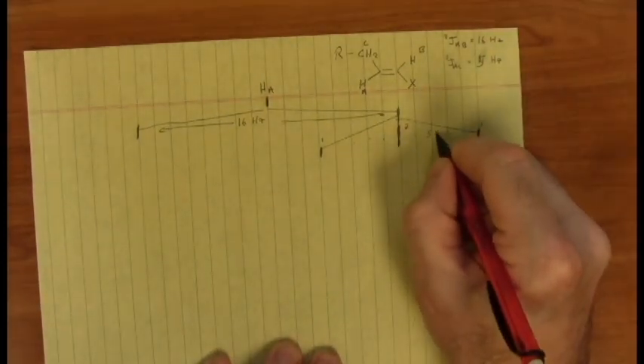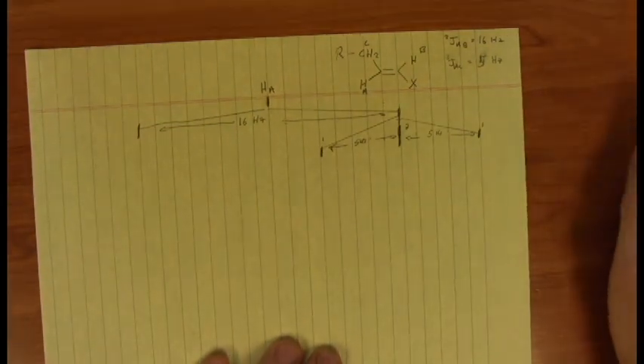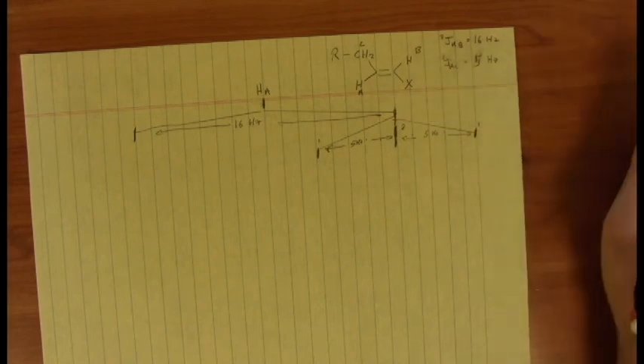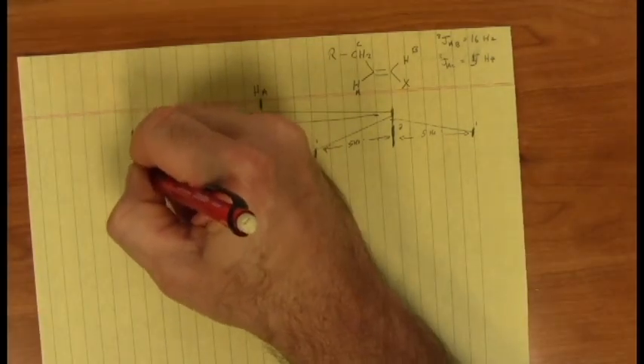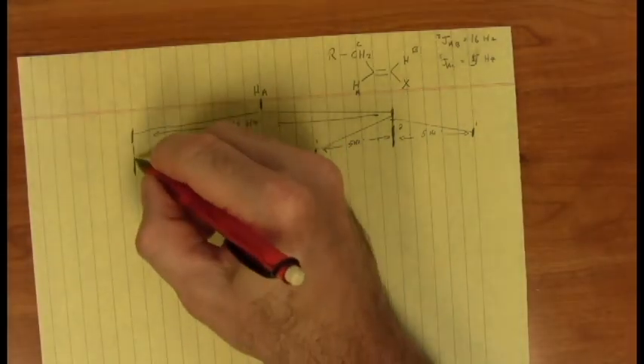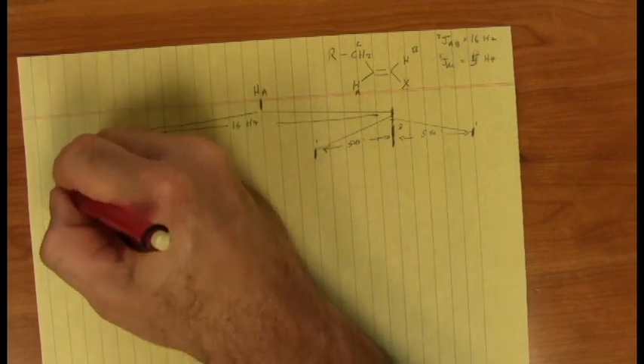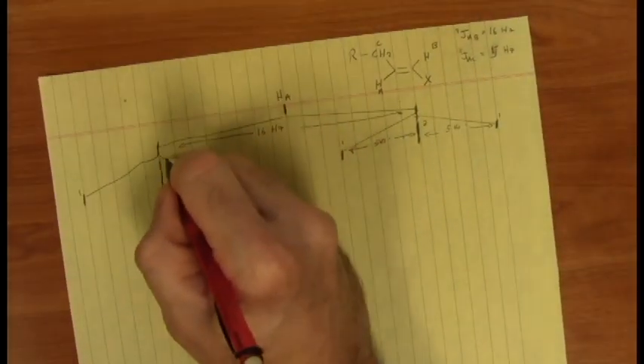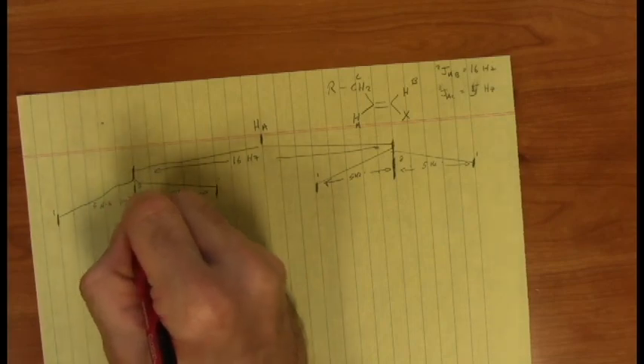Again, whatever I did on this branch, I do on this branch. So away we go again. We mark the center position. This is a triplet. And then we count over. 1, 2, 3, 4, 5. 1, 2, 3, 4, 5. Okay. And connecting everything up. Nice and pretty once again. Oh, that wasn't very pretty, but you know. Oh, well. We'll just let that one go. So, triplet. 1 to 2 to 1. 5 hertz. 5 hertz.